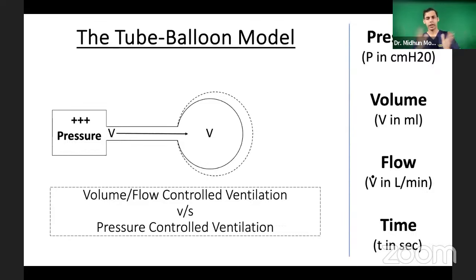All right. Then we have volume control ventilation. So either I can tell the ventilator that I want it to deliver this much volume. Suppose I want the ventilator to give the patient 400 ml of tidal volume. Let's say the machine generates around 10 centimeter water of pressure to deliver 400 ml of tidal volume, right? Now I tell the ventilator to deliver 500 ml of tidal volume. The machine will generate a higher pressure, maybe around 15 centimeter water, to deliver this higher volume.